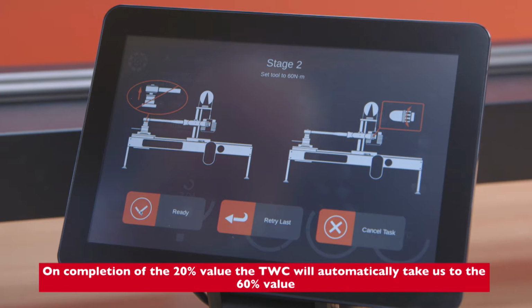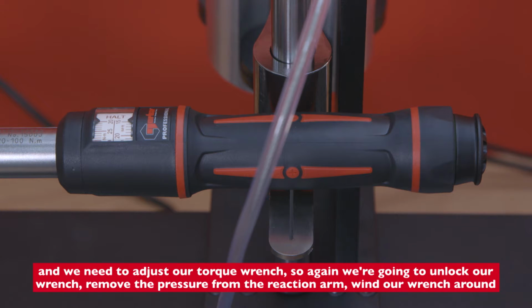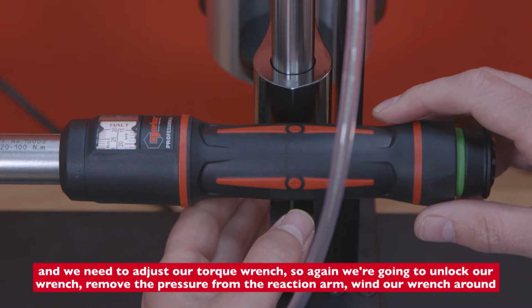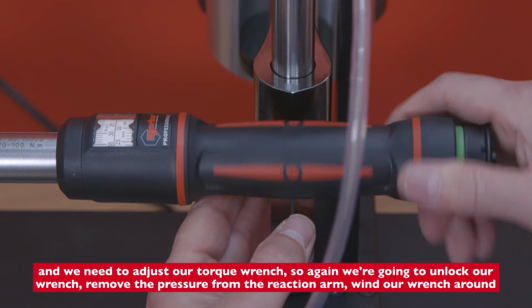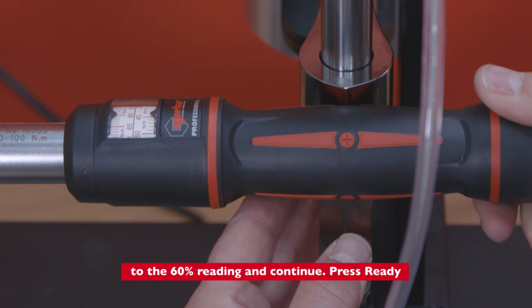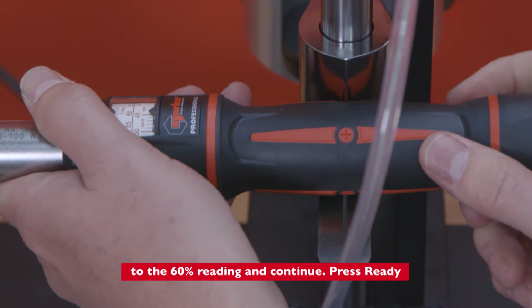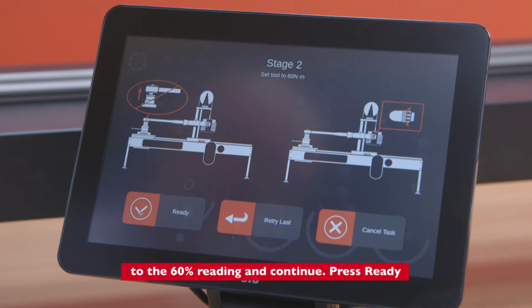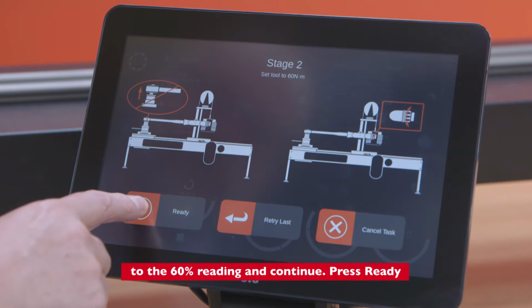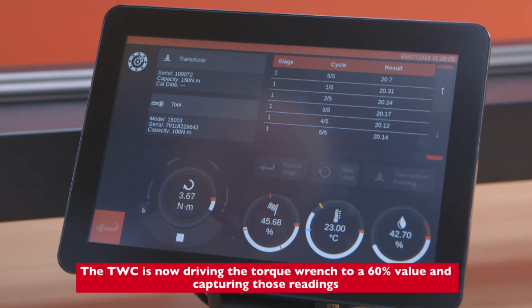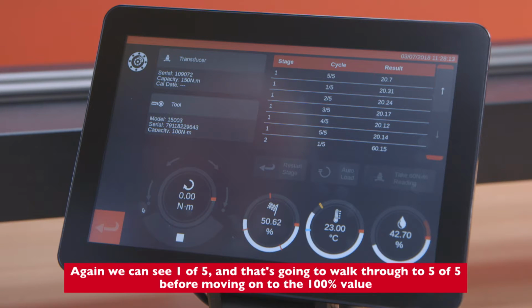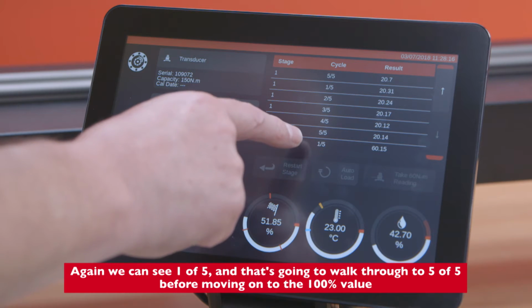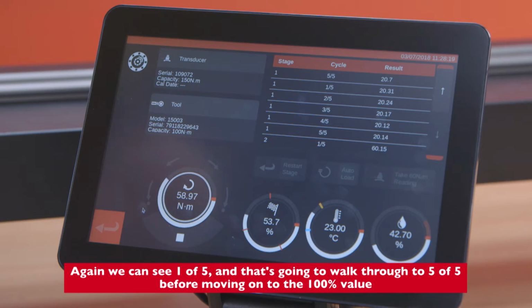On completion of the 20% value, the TWC will automatically take us to the 60% value, and we need to adjust our torque wrench. So again, we're going to unlock our wrench, remove the pressure from the reaction arm, wind our wrench around to the 60% reading and continue. Press ready. The TWC is now driving the torque wrench up to its 60% value and capturing those readings. Again, we can see 1 of 5, and that's going to walk through to 5 of 5 before moving on to the 100% value.